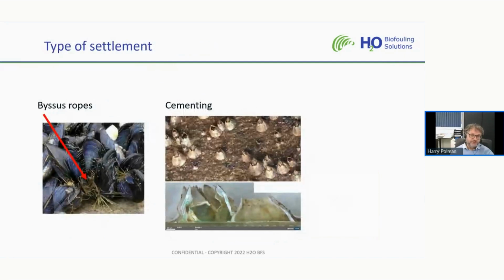When these organisms settle, they settle in two different ways. Some organisms, like mussels, use biological ropes, we call them byssus ropes, to attach to the pipe surface. The picture on the left, you can see very clearly these ropes. These ropes are very strong. But once you kill the animal, so once you kill a mussel, these ropes will dissolve and the shell itself will detach from the surface and flush out of the system.